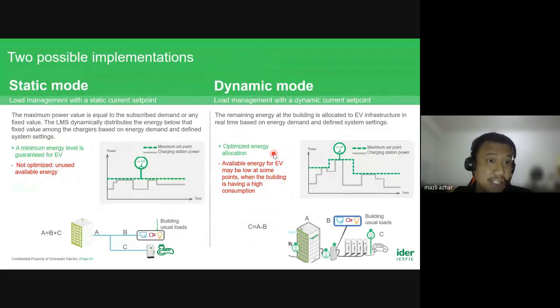So they have two types, as I mentioned, static mode and dynamic mode. In static mode, you will have a current set point to ensure you don't exceed. For example, normally a car will be charged using 16 amps or 32 amps, which is either 7 kilowatt or 11 kilowatt. Using static mode, you set in the system that for this electrical charger, you will not go up to 7, you will go to 3.5 or 3.4 only for the whole day.